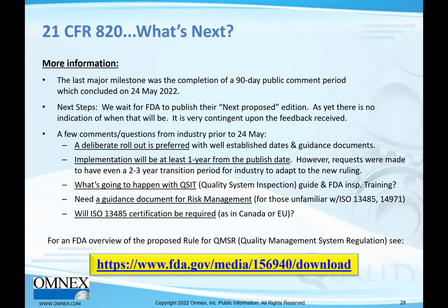Right now, 13485 is a voluntary conformance to a standard. Once 13485 rules are incorporated into CFR 820, it becomes a compliance. You'll need to comply in order to meet the requirements of the FDA. It doesn't require certification, but it requires compliance. I hope that helps clarify that.